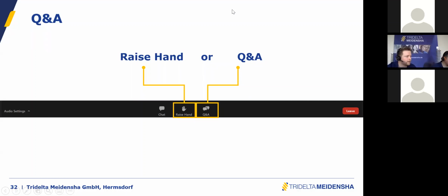Okay, we were aware of situations like this, so that's why we have included the download for the Excel. Yes, you are right. In the smartCOUNT cloud, the magic happens where third harmonic current is calculated to resistive current, and this is of course the more correct way to do the monitoring. In the Excel file, you will only have the raw third harmonic value, which can also be used to do the monitoring, because you are not really interested in absolute values. You are interested in the surge arrestor leakage current trend.